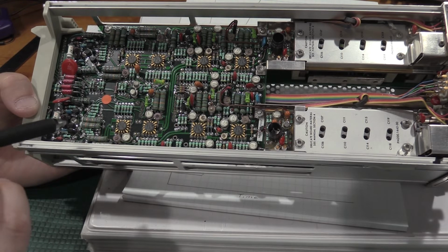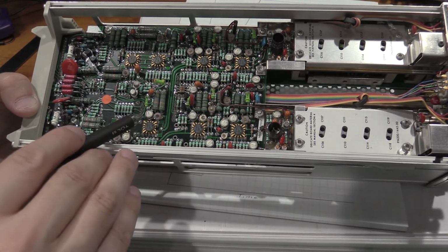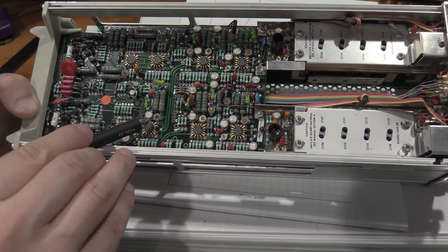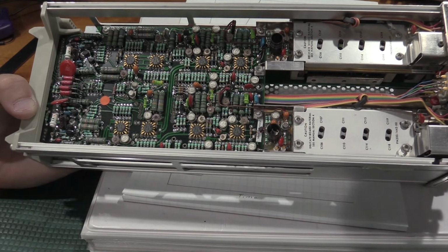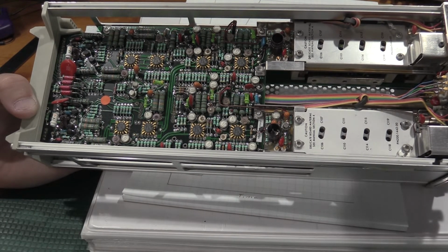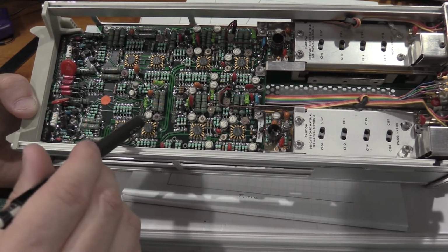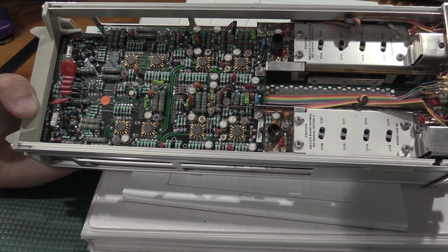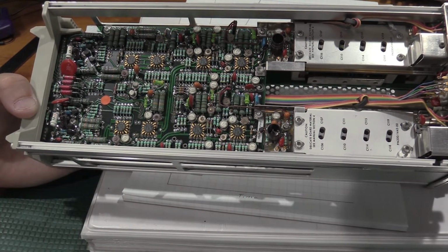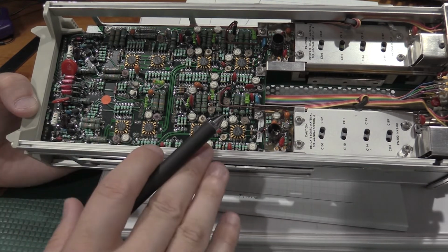So the other thing is these RC networks, because they're filters, they're very sensitive to these capacitors going open. I have seen scopes, and I've helped other technicians with scopes, where they've been down 60 megahertz on bandwidth, 100 megahertz on bandwidth, because some of these trimmer capacitors have opened up and they're no longer acting as capacitors, they're just open circuit.